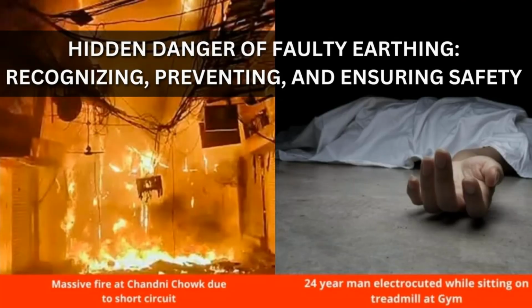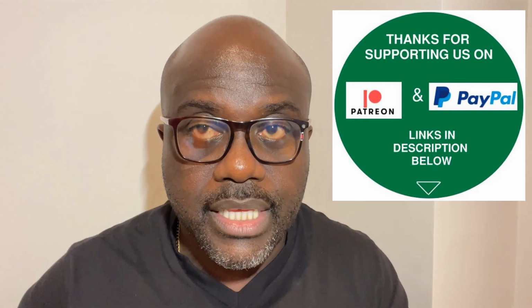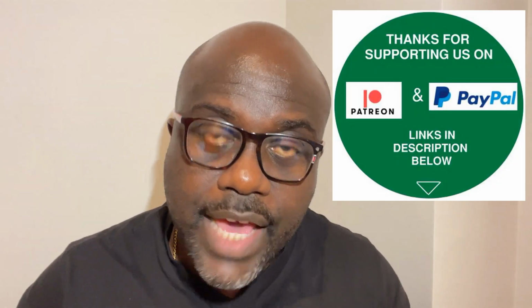And finally, guys, most electrical fires are completely preventable. They happen because defects are hidden, ignored, or misunderstood. A new house is not automatically a safe house unless the electrical systems have been tested, verified, and you have a commissioning certificate, let's say. If you don't inspect, test, and design properly, in fact, I'm going to do this the other way around: you have to design properly to start with, then inspect and test. If you don't do all those things properly, then you're relying on luck, and luck can run out. So this is important. Hidden electrical defects. Hope everything made sense.